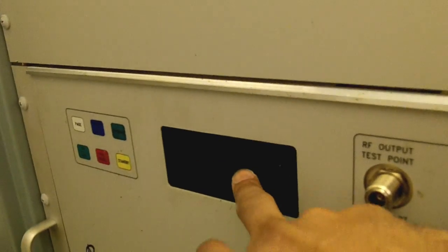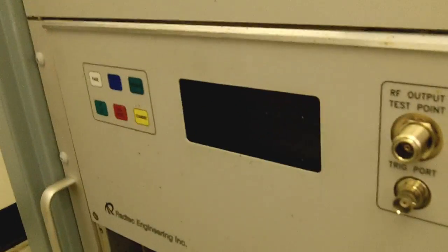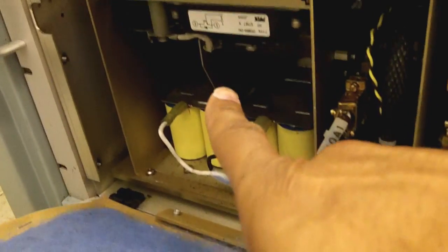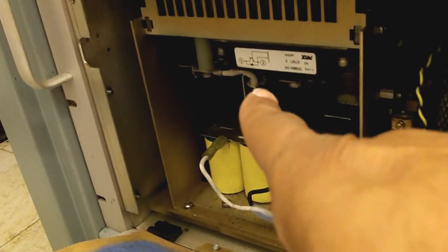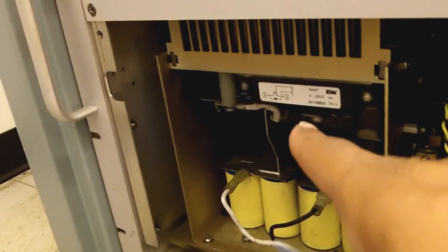Okay, we found some major problems with this transmitter down here. I'm over here checking on everything and somehow everything goes quiet. I look down here on my display and everything shut down now because of the very high voltage. But we had some over temperature alarms on here. Come checking everything around this high voltage power supply right here, which is over 1,000 volts, like 1.4 kilovolts. The cooling fan on here is dead.